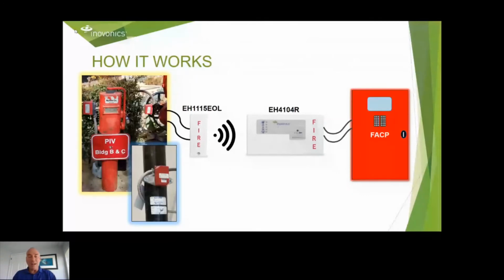Another application which could save a lot of money is, let's say there's a monitored commercial fire system in a main building, and then a new building is put up where there's a separate outbuilding on that commercial site. It's a separate building, and there's a fire system, but it has to be monitored, but there's no wiring for the signaling or the monitoring infrastructure. What you can do is take this EH1115 EOL transmitter and put it on that remote building's fire panel alarm output. And that would report to this receiver in the main building's fire alarm panel. So if there's a fire in the remote building, that would report to a zone on the main building's panel, and that is acceptable from a UL864 standpoint.